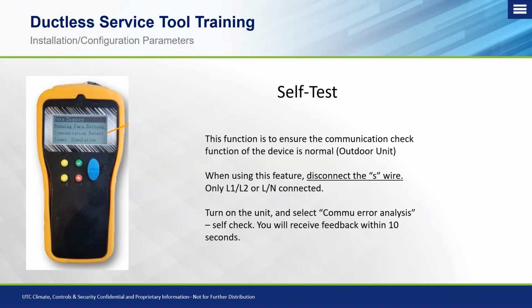Okay, once you get that self-test menu on there, typically it takes about 10 to 15 seconds, and it will say either the device is communicating properly or that there is an issue. If there is an issue, this could be further credibility that there actually is something going on with the outdoor board, which could be the reason that you're out there.